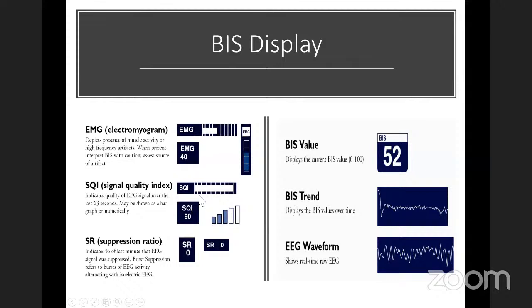Similarly, there is a signal quality index, which may be shown by a graph or numerically. This is also important to indicate the quality of the signal over the past 1 minute. Then there is a suppression ratio, which indicates the percentage of the last minute that the EEG signal was suppressed. And this burst suppression refers to the burst of EEG alternating with the isoelectric EEG.